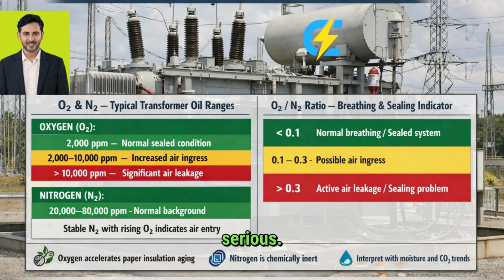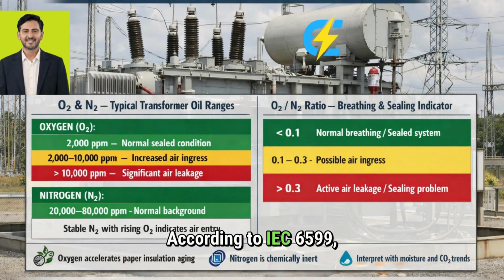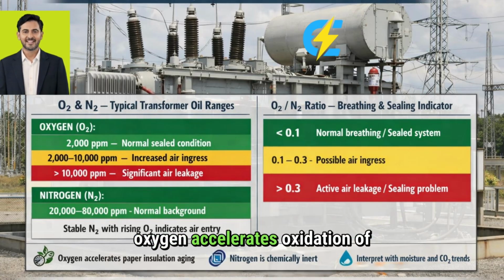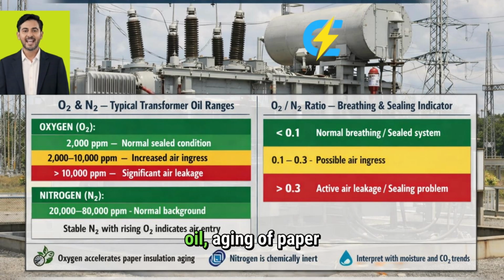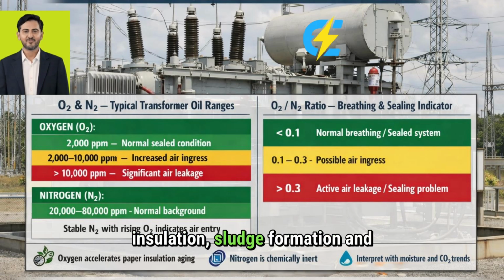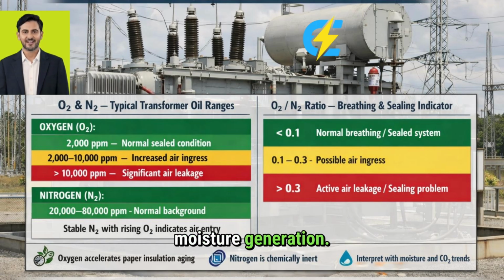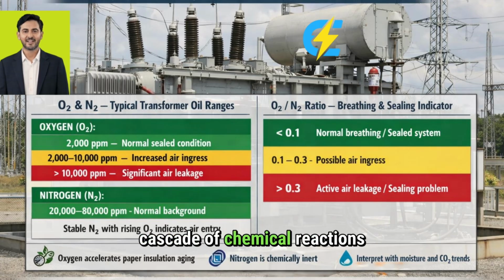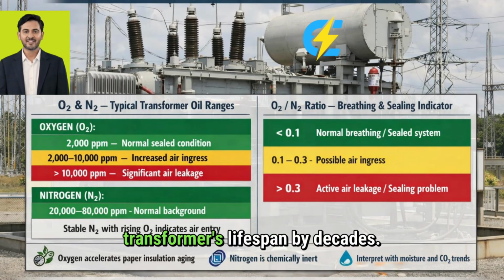Here's where things get serious. Oxygen itself does not cause faults, but oxygen is a powerful aging accelerator. According to IEC 60599, oxygen accelerates oxidation of oil, aging of paper insulation, sludge formation, and moisture generation. Oxygen plus heat plus moisture is the worst combination for transformer life. This combination creates a cascade of chemical reactions that can reduce your transformer's lifespan by decades.